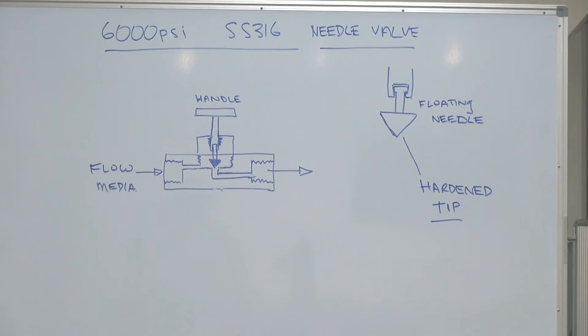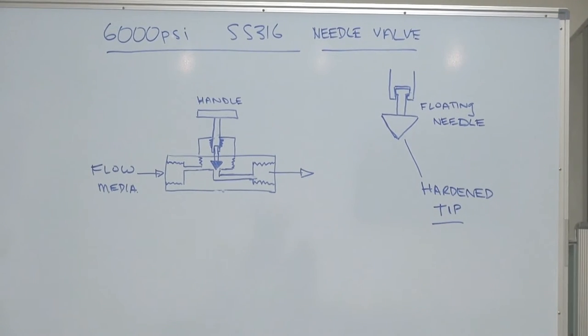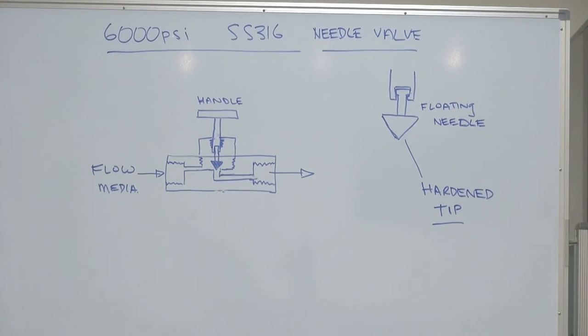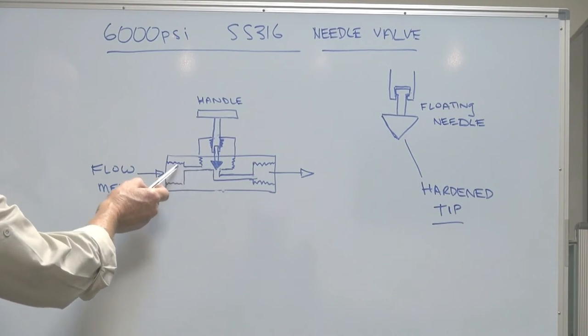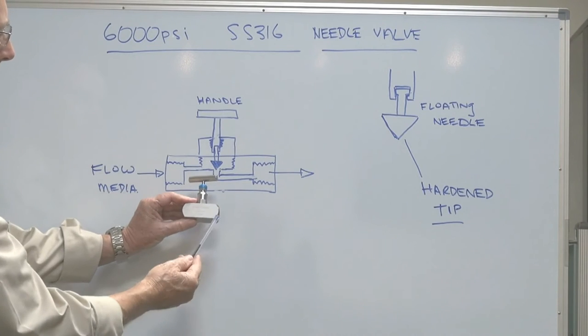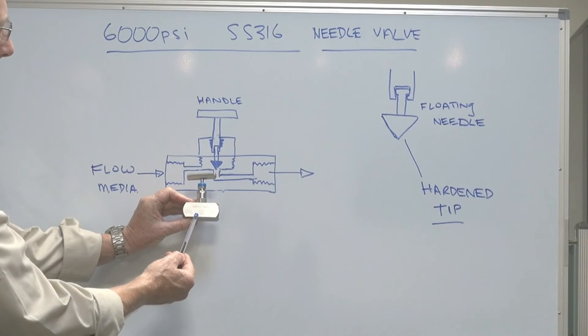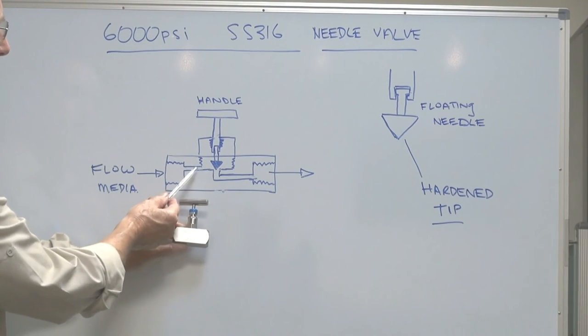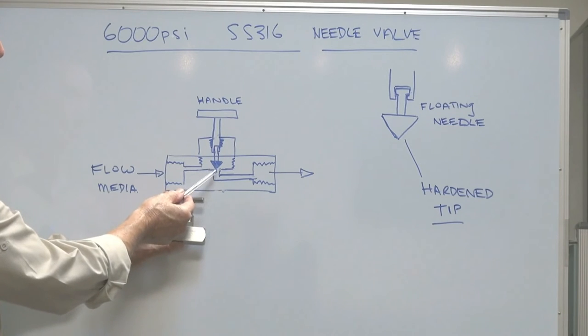If you had low pressure, say 300 PSI, it won't make a difference - you still pipe it up the same way. It does have a direction of flow on the outside of the valve, etched into here with the pressure rating and sizing. The flow will still go on the top and down through that way.